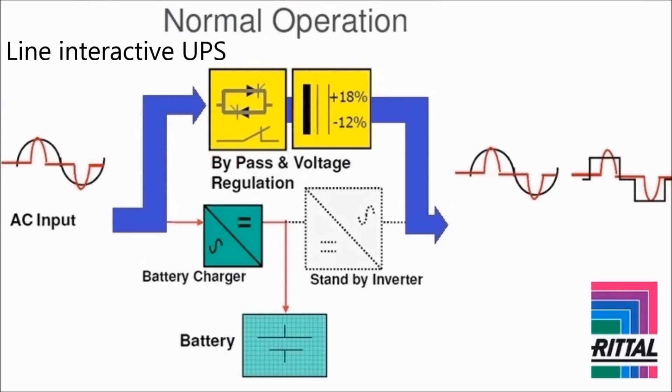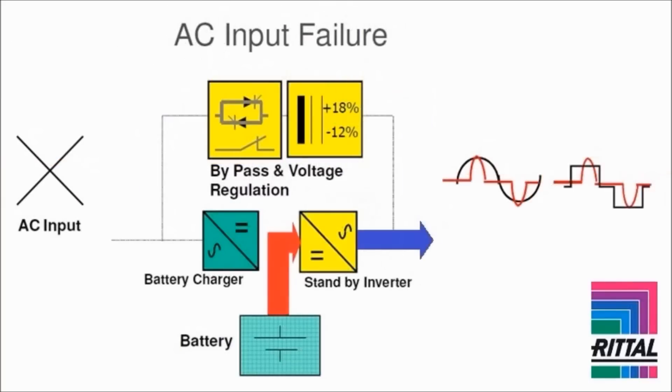A better UPS solution for a data center, compared to the standby UPS, is the line interactive, or interactive, UPS. There are models of this type of UPS with either modified sine wave output or true sine wave output, which is the only output type appropriate for a data center.